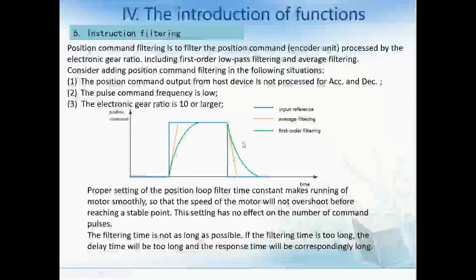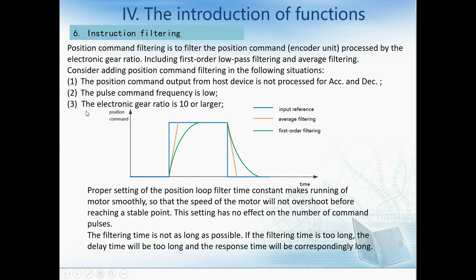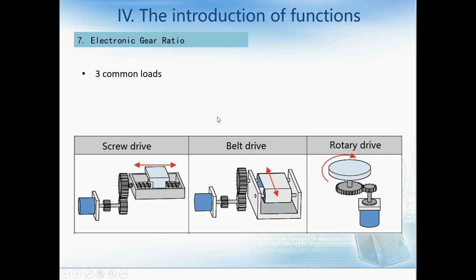Now we talk about filtering. Command filtering is used to filter the command processed by the electronic gear ratio, including first-order low-pass filtering and average filtering. Consider adding command filtering in three situations: when the command output is not processed for acceleration or deceleration, when the pulse command frequency is low, or when the electronic gear ratio is 10 or larger. The first-order filtering has the smoothest curve, resulting in the least vibration. Note: if the filtering time is too long, the delay time will be too long and response time will be extended. For the three common loads, we need to set different gear ratios according to the application.